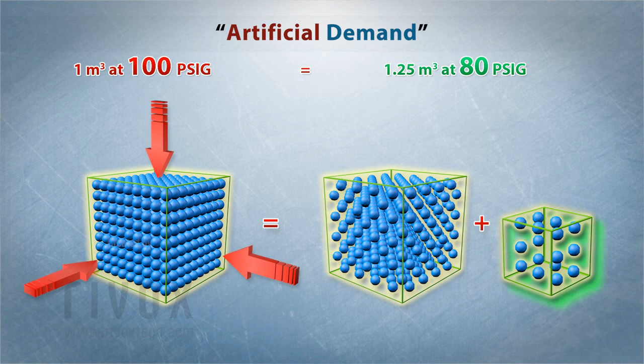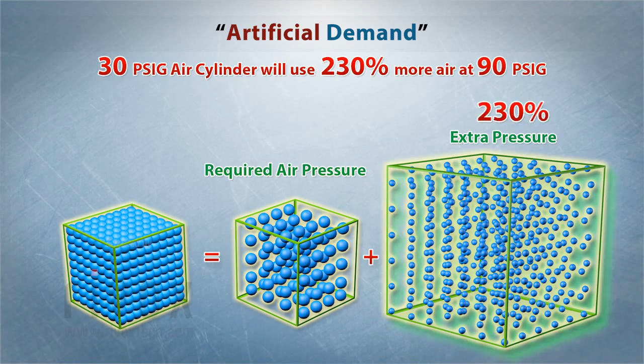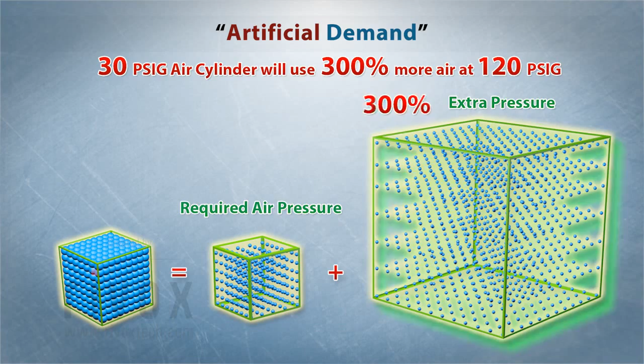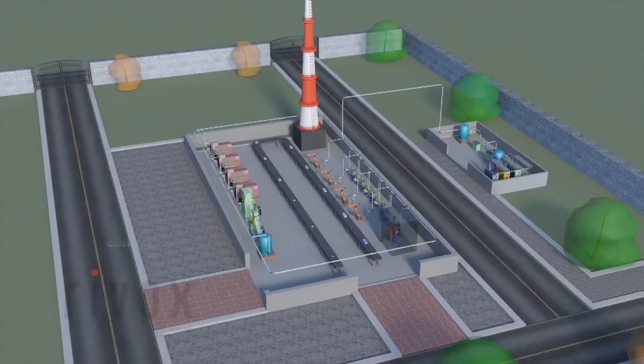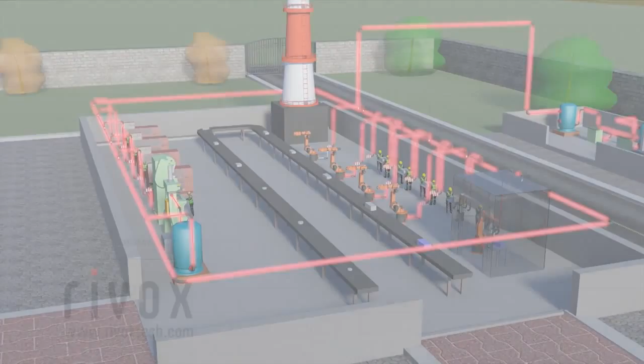In industries generally, an air cylinder that is specified to use 30 psig will use 70% more air at 60 psig, 230% more air at 90 psig, and 300% more air at 120 psig. Virtually all air-powered equipment work this way. The more pressure delivered, the greater the air used. Auditors call this phenomenon artificial demand, resulting in higher energy consumption.